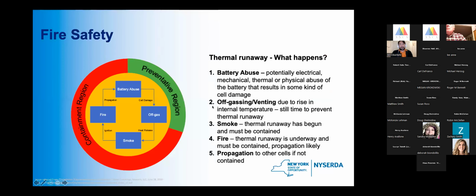This is thermal runaway, which is what I was talking about. That's the purpose of the 9540A test, to send the battery into thermal runaway. Let me explain what thermal runaway is. Remember, we have the cells, the modules, the racks. Thermal runaway is when a cell starts to rise in heat exponentially. Once that process begins, it cannot be stopped. So we're not trying to stop thermal runaway anymore, we're trying to make sure it doesn't spread. That's typically how firefighting works for energy storage systems. Once something is on fire, we're not worried about it anymore, it can't be used again. We're just trying to contain that event. It's a containment thing.